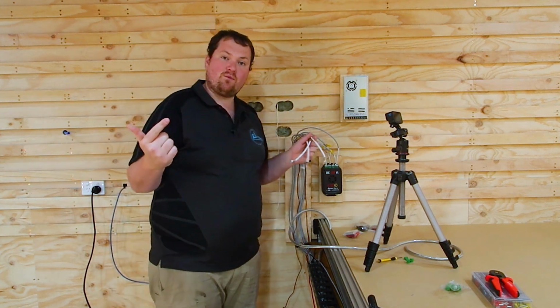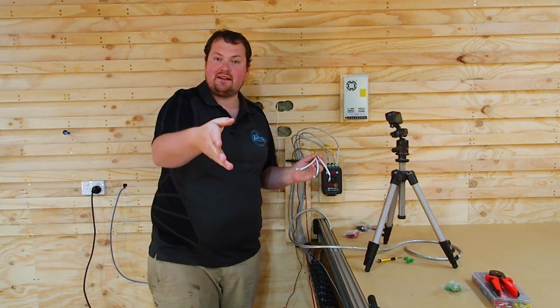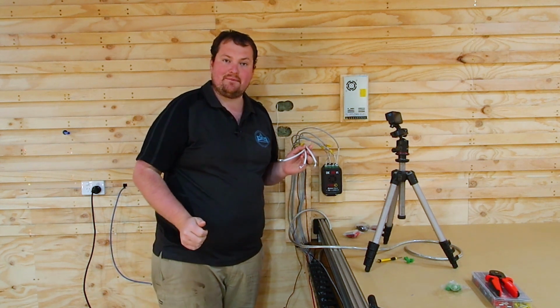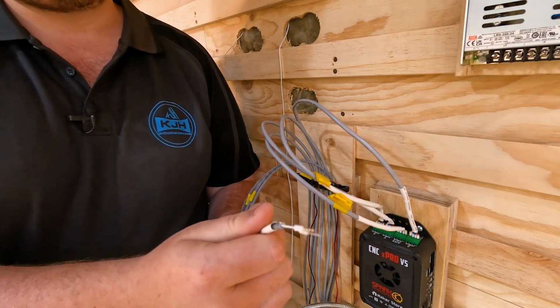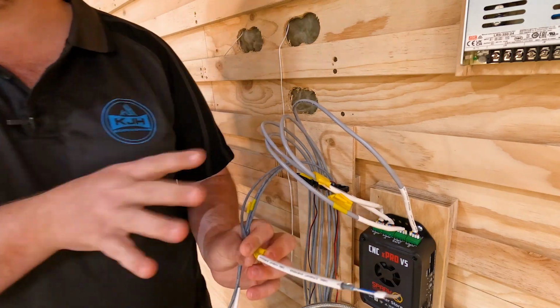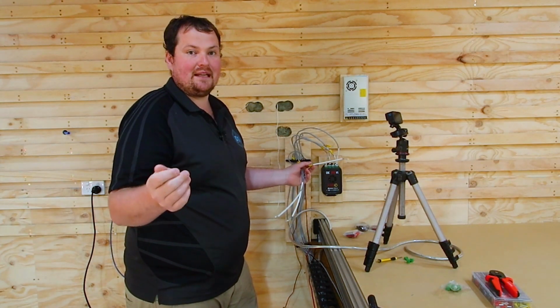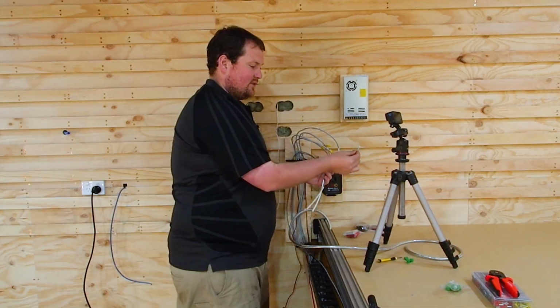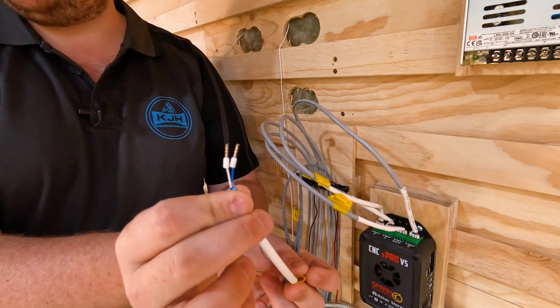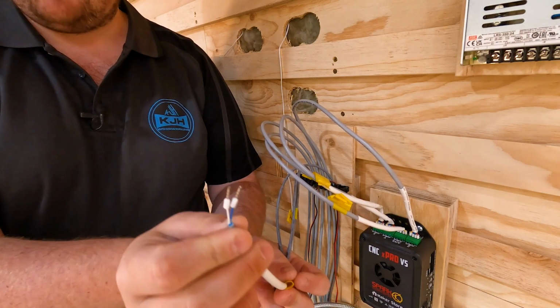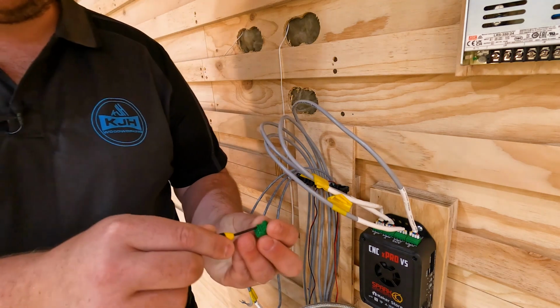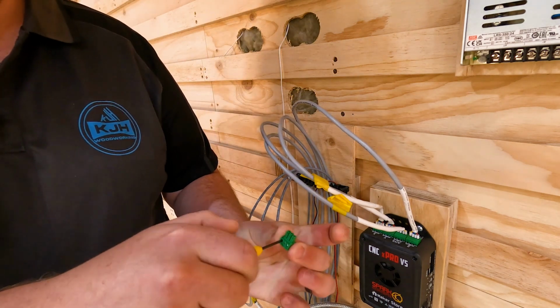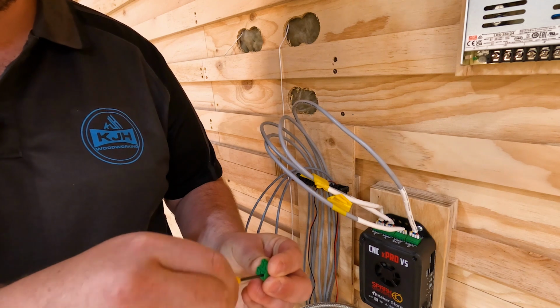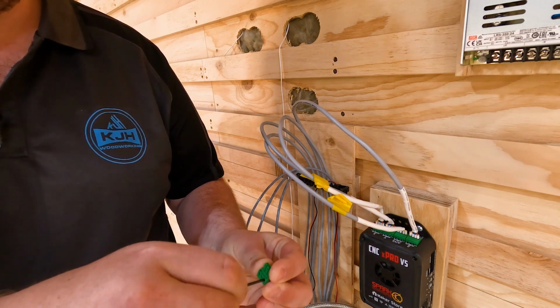We're going to start with wiring in at the controller end, then we'll fit them off down at the machine end. I've gone ahead and stripped the cables in the exact same manner as we stripped the previous cables. However, you'll see that there's only 2 wires coming out of the limit switch cables, a blue and a white. So with your limit switches you have a 3-prong connector, but you only need to use the outside points.